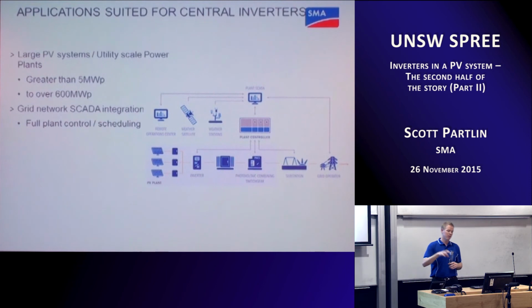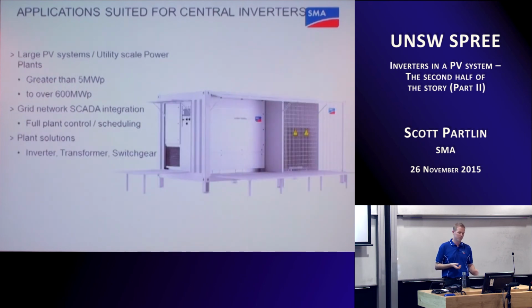And as a result of that, these sorts of plants need to be directly integrated into a utility's SCADA system, which is their supervisory control and data acquisition system, so that they can have direct control. Rather than letting the inverter detect islanding conditions, they're communicating directly with the inverter, and they will tell the inverter when it might need to switch off or when it might need to change its power, when it might need to schedule to ramp up or ramp down, when it might need to provide certain levels of support, be it frequency or voltage or fault ride through or other things like that. So when that becomes a requirement and we're at that size, central.